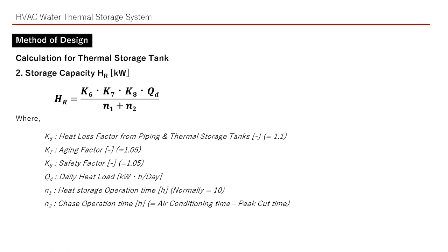Next is the storage capacity HR. We can calculate it from this formula. K6, K7, K8 are the factors for each. Qd is the daily heat load. N1 is the heat storage operation time — normally it is 10 hours. N2 is the chase operation time. If the chase operation time is short, the thermal storage tank will be bigger.